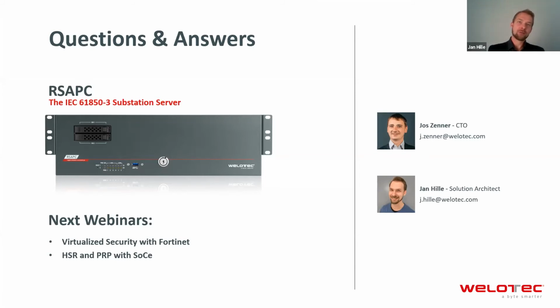You may already have a redundant setup in your substation, meaning you have, for example, 6 boxes: an HMI, a gateway, log server, substation automation system. And the easiest way you have now is you have 2 of each. This is pretty much the easiest way in a virtual environment as well, meaning you have those 5 or 6 boxes, you virtualize these boxes and put it on one substation automation server, on one RSAPC.